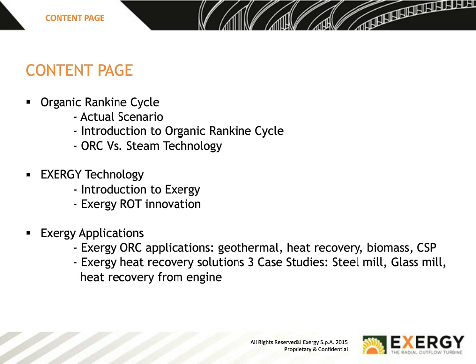So we have a question here regarding the steam cycle being used as superheated or supercritical. The type of cycle we use is generally not a supercritical cycle with our type of turbine. That doesn't mean it's impossible. However, when you do a steam turbine cycle, you always generally go superheated because you need to have superheat in order to recover enough energy in the steam turbine. It's not so essential to go to such levels with the organic Rankine cycle. But that doesn't necessarily affect the overall efficiency of the heat recovery system.